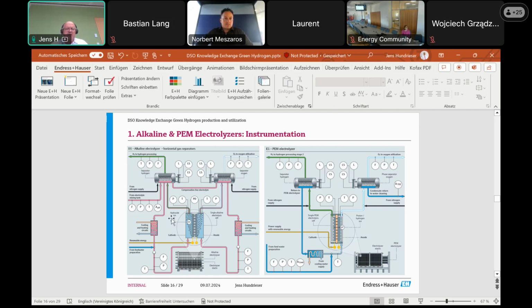One thing I can say: when you have 100% hydrogen, not 10%, pressure devices need very thin membranes with gold coating to last a long time. So on one side we have the differential pressure with gold coating.